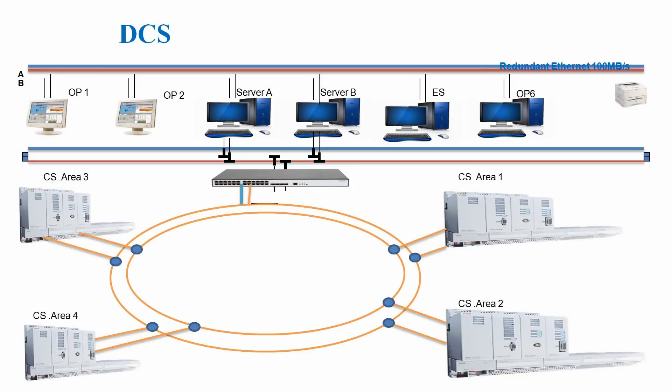On that LAN network we have the operator station, engineering station, servers, and even a printer. The main concept is that in area 1, area 2, area 3, and area 4, each has its own controller. Not only one controller per area — you have redundant controllers. In area 1, for example, you have two controllers: one is the main controller and one is redundant. If the main controller fails, the redundant one will take over. Same for area 2 — you have a main controller and a redundant controller. This is the beauty of the DCS.